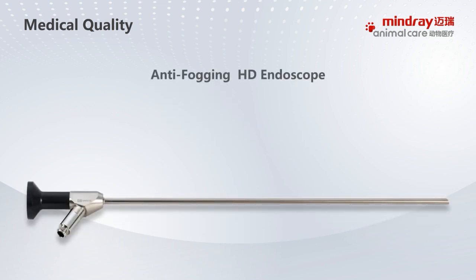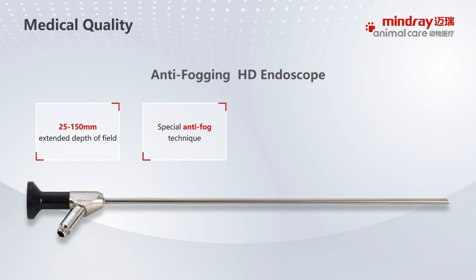So we can provide the anti-fogging HD endoscope. We have the advantage of, first, the extended depth of field. So you can see the range is from 25 to 150 millimeters. Then you have the special anti-fogging technology. As we know, if the endoscope gets into the animal's body, because of the temperature difference, there will be foggy moisture on the front of the endoscope. So by using such a special anti-fogging technology, we can reduce the time fog stays on the endoscope. Can provide better image quality to the veterinarian.